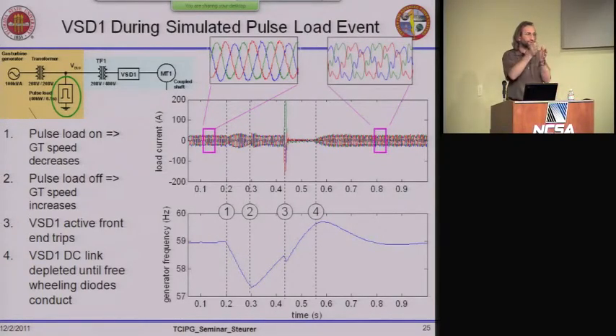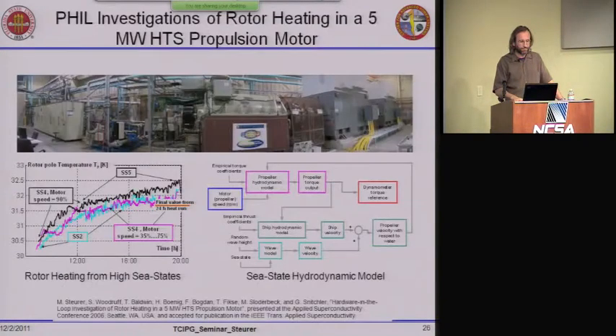The power electronic switches are configured such that there's a diode rectifier operation when you don't fire the switches. At the end of the day, you had a diode rectifier sitting on this grid, and if you don't catch that, under such conditions you may end up with a diode rectifier and not even notice it. This is where power hardware in the loop simulations can really shine.